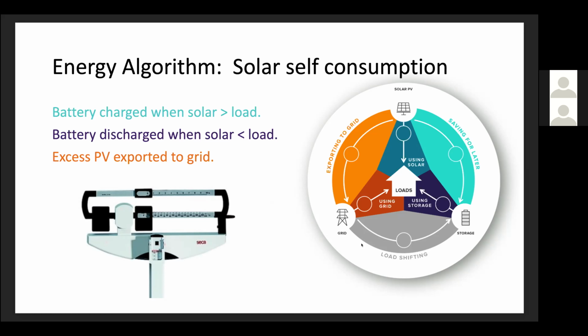Unless there's more excess PV than what the battery is able to charge. And the battery can only charge or discharge while grid tied up to 5 kW. And if there's more than 5 kW excess PV, then any excess PV will be exported to the grid.